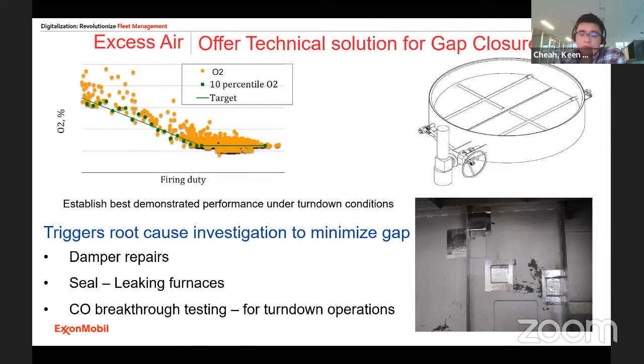So what it helps to do is trigger a root cause investigation to help minimize those gaps. Tighter control on stack O2 through improved maintenance practices is achievable. In this case, the site managed to adopt and deploy good maintenance practices around damper maintenance, because it was found that more often than not, the dampers could not be adjusted as they were not working properly. With improved damper maintenance, they were able to reduce some of the excess O2.